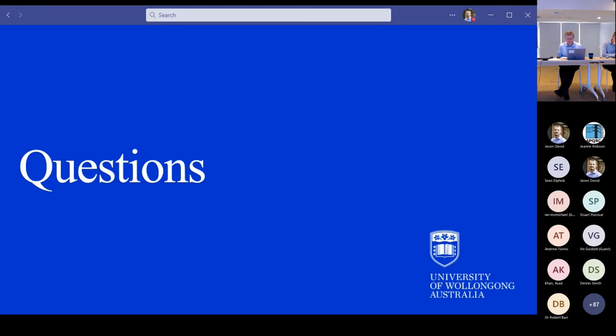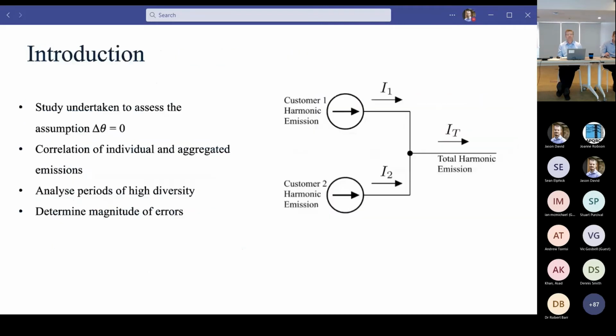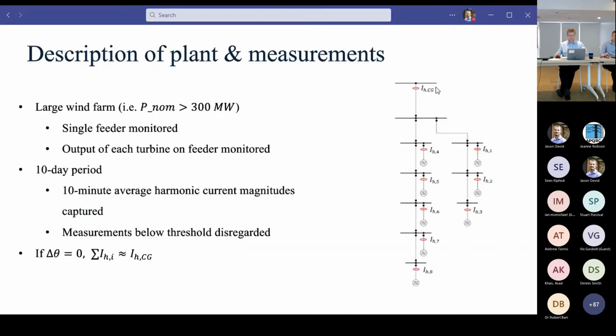A slightly less controversial one perhaps: how and where did you measure the harmonic current, noting that the background harmonic current will also have an impact? Let me jump back so I can talk to it a little bit. This bus we can see at the top here is a collector bus that had a number of different feeders connected to it. The individual monitors, now what's not shown here are the step-up transformers for each of the individual generators, so these monitors existed on the LV side of those transformers. So we had to scale the currents down to the increased voltage of the collector network itself. And this was taken right at the bus bar, at the far end of the collector feeder itself.